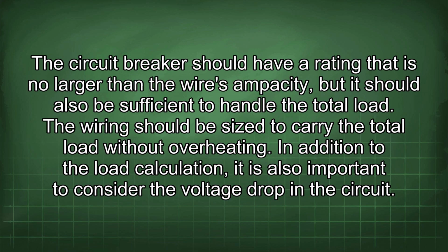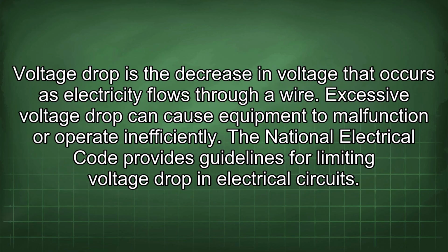The circuit breaker should have a rating that is no larger than the wire's ampacity, but it should also be sufficient to handle the total load. The wiring should be sized to carry the total load without overheating. In addition to the load calculation, it is also important to consider the voltage drop in the circuit. Voltage drop is the decrease in voltage that occurs as electricity flows through a wire.